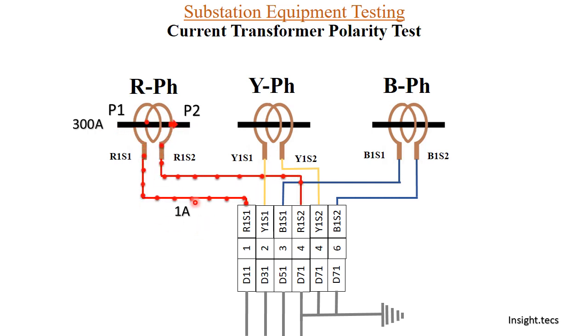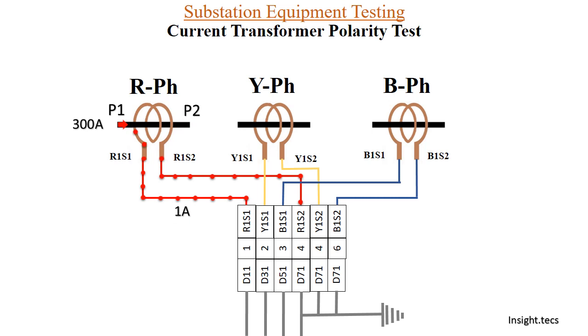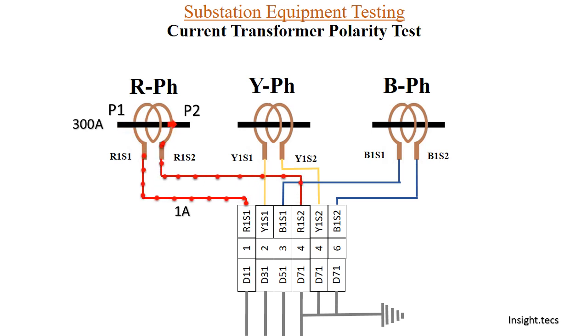Whenever 300 amperes flows through the primary winding, on the secondary side we are getting 1 ampere because it is connected between 1S1 and 1S2. It is important to note that whenever the direction of current flow is from P1 to P2, the current will be flowing from 1S2 to 1S1. This is the basic polarity of the CT, and now we will check if the CT polarity is correct or not.